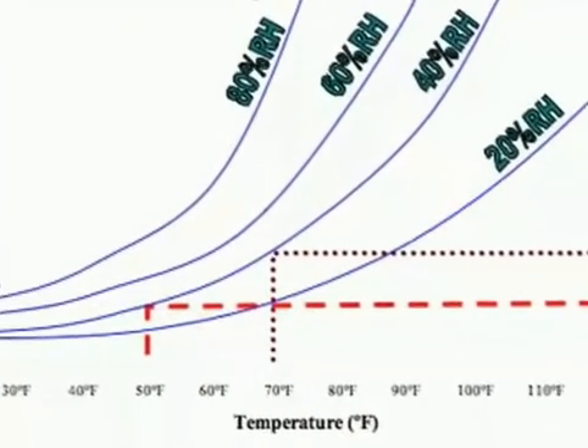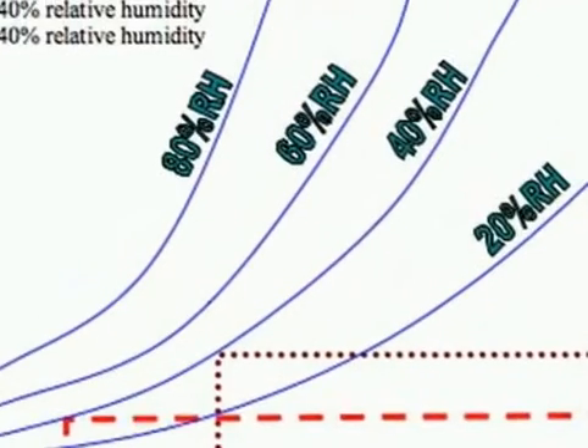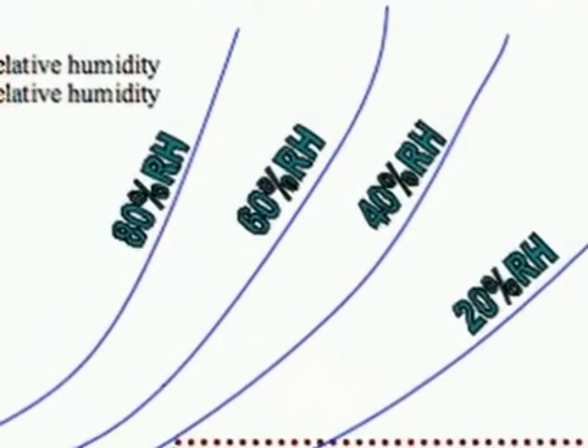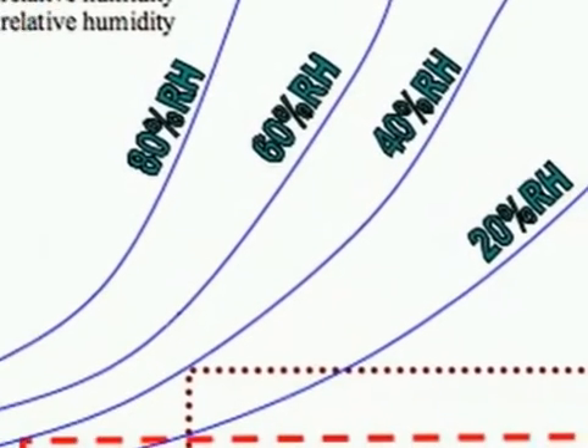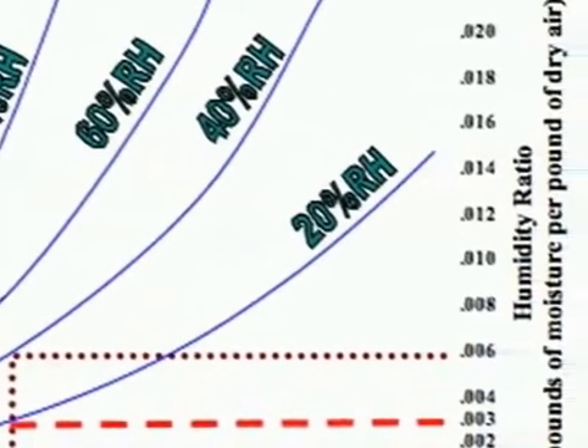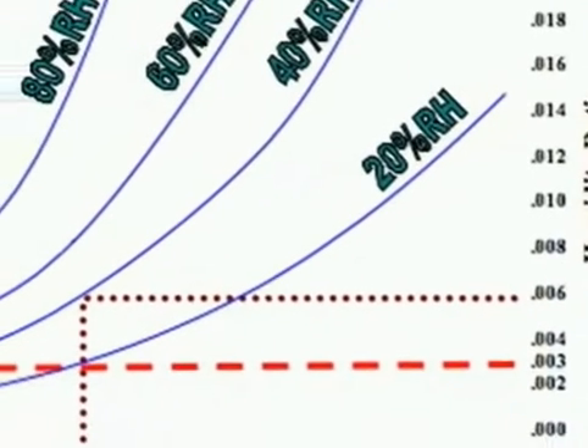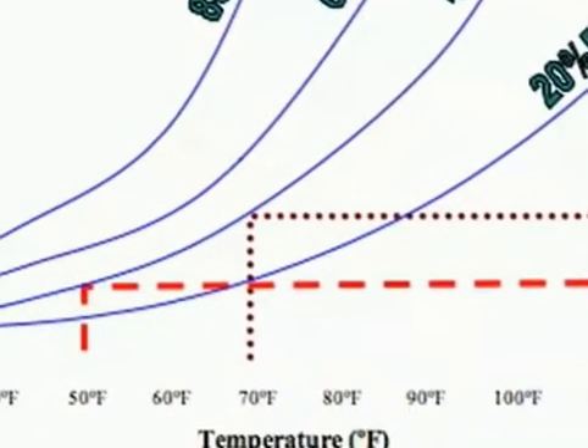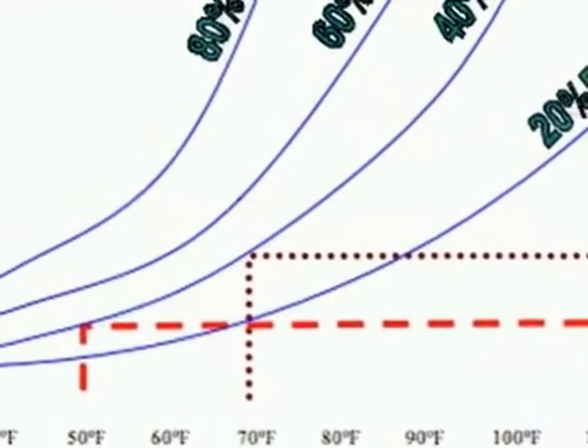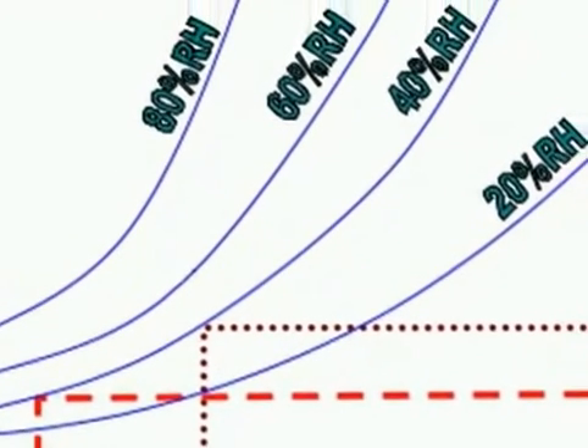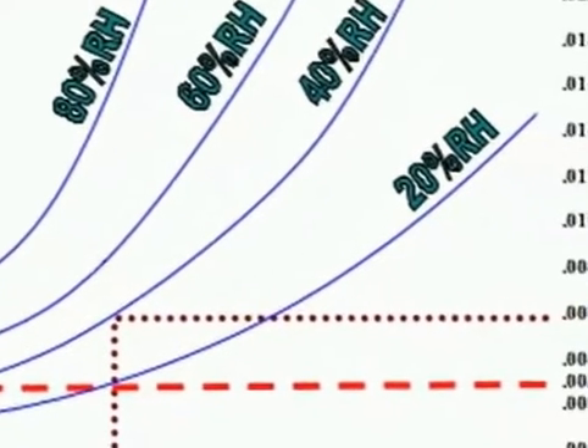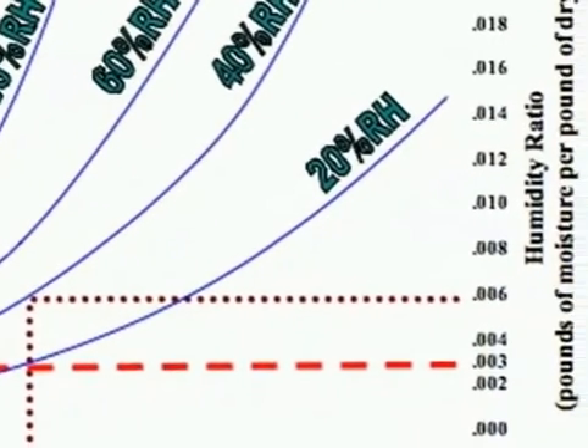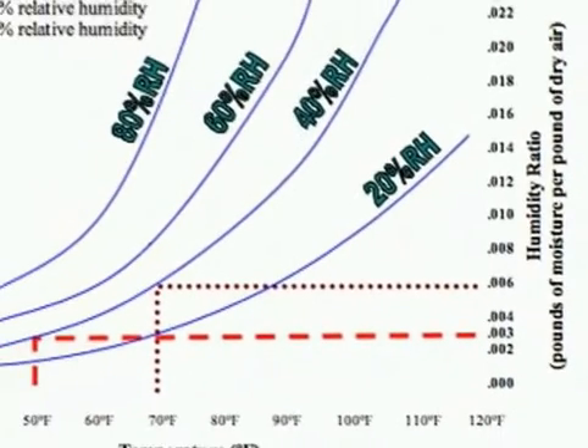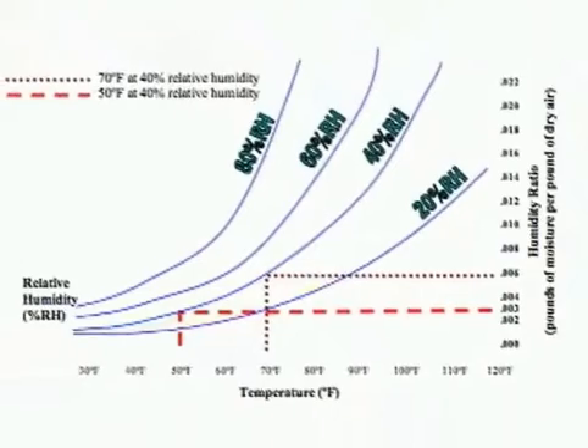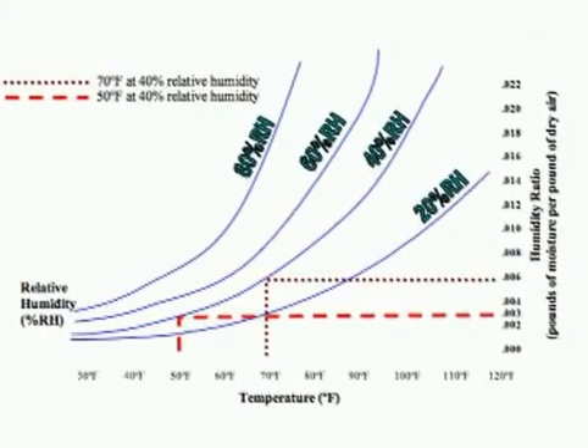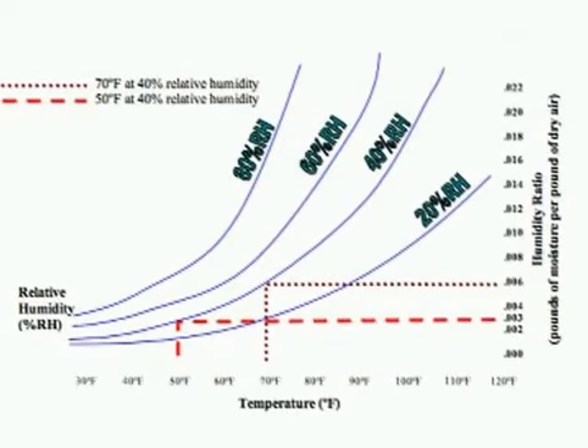The chart shows that air at 70 degrees Fahrenheit and 40% RH contains approximately 0.006 pounds of moisture per pound of dry air, as indicated by that bold line going across horizontally. While the air that is at 50 degrees and 40% RH, same RH, contains approximately 0.003 pounds of moisture per pound of dry air, as indicated by the other line. Although both are at 40% RH, the 70-degree air contains roughly twice as much moisture as the 50-degree air.